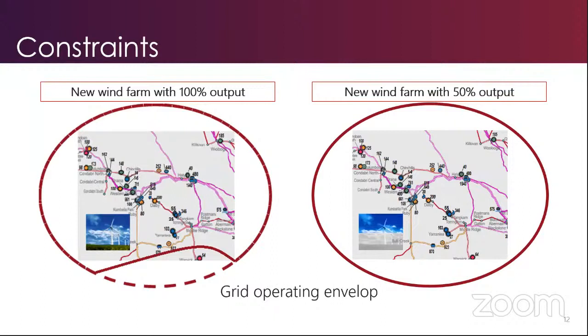Through the studies I mentioned earlier, we identify these kinds of situations and develop constraints to apply during operation. This could mean that a particular wind farm, under a particular grid operating condition, might not be allowed to operate at 100% - it might be constrained to 50%. It could also mean that, under that condition, we might be constraining a few other generators in the area as well, just to maintain that grid operating envelope.